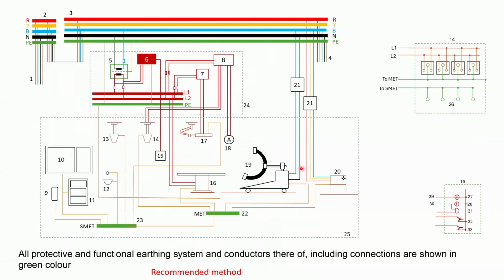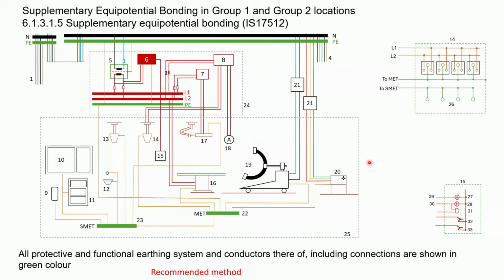How to use a medical IT system is very much explained. Unfortunately, there are companies supplying medical IT systems, and these companies are also demanding a separate earth pit, which is absolutely wrong. So my advice to everyone in the medical field is, if any supplier, be it a transformer or a generator or a panel board or a lift or a medical IT system or a biomedical equipment, if any of these manufacturers are demanding a separate earth pit, the best way is you immediately conclude that this gentleman or this company doesn't have any idea of the electrical installation. So better you stop working with these companies. Otherwise, you will be in trouble. There is absolutely no requirement of a separate earth pit in any of these locations.